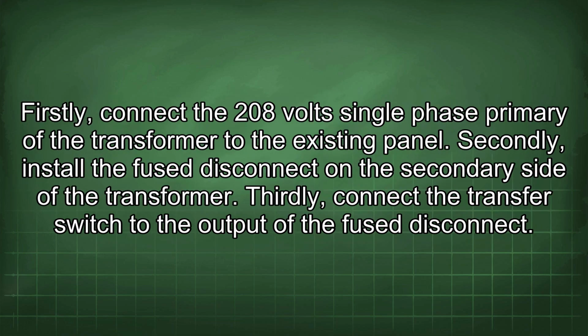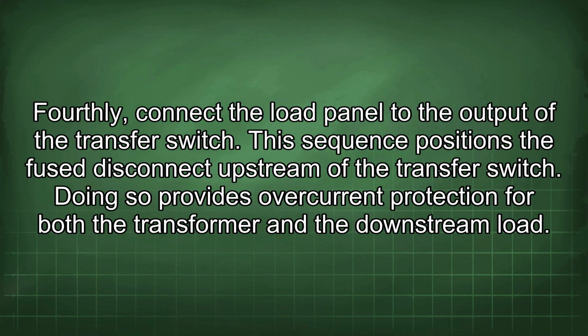Firstly, connect the 208-volt single-phase primary of the transformer to the existing panel. Secondly, install the fuse disconnect on the secondary side of the transformer. Thirdly, connect the transfer switch to the output of the fuse disconnect. Fourthly, connect the load panel to the output of the transfer switch.